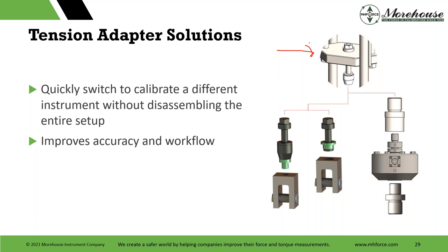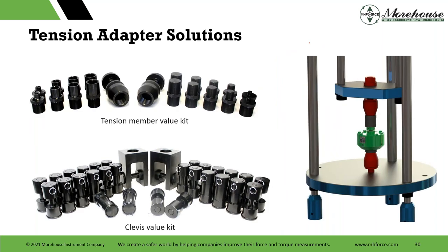It quickly switches to calibrate different instruments without disassembling the entire setup, and improves accuracy and workflow. Hey, the amount of time you can save, not only is it a time savings, but for those out there that are Caltechs, it's just so much easier for you, if you're doing these calibrations and breaking down and doing all these different tension setups. Typically, some things we do in our lab, this bottom piece can just stay in there if you have a good tension setup, and just leave it in the machine.